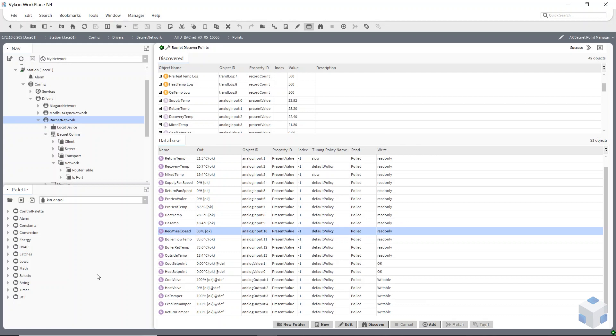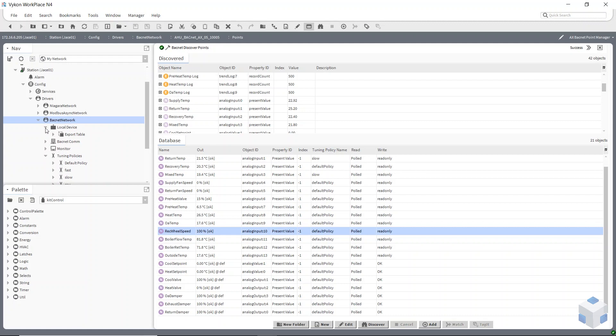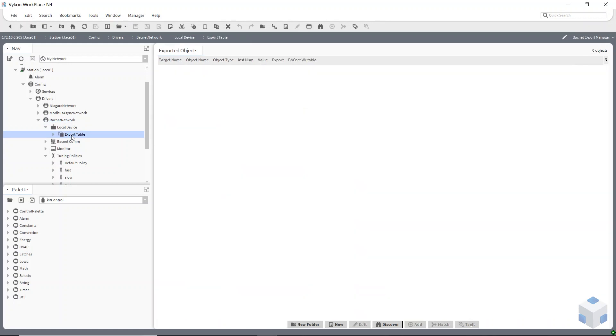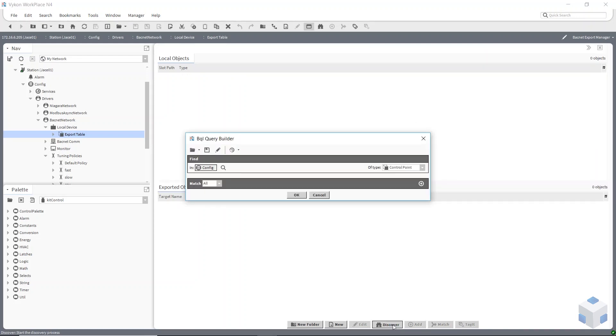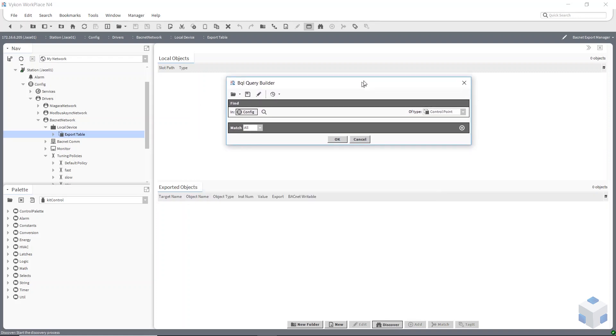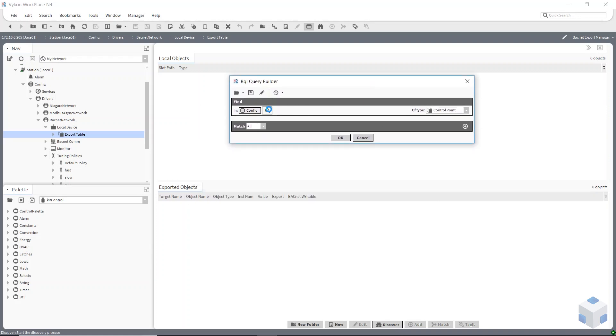Last thing I was going to quickly show you was how to expose points on your device. So if you unfold local device in your tree here in your subnetwork, sorry in your nav sidebar, and then click on export table. So now I've got a discover at the bottom again but this time when it does the discover it's actually going to come up with my BQL query builder and I'm going to be discovering points on my Jace. So I can now say I want to find, I know that I've got a couple of Modbus points here.